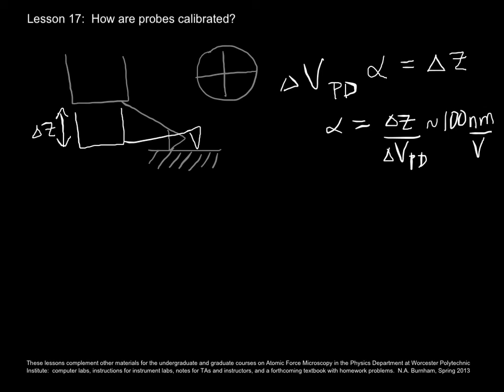To find the deflection, then, what you do while you are doing your experiment is you reposition the light spot in the center of the photodiode when the cantilever is free from influence of the sample. And your deflection is then your calibration factor times whatever voltage change you see during your experiment, right? Not during the calibration.